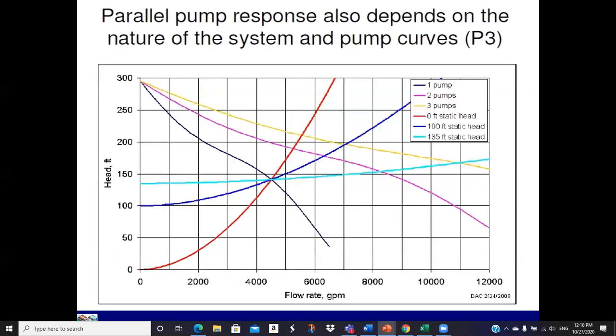So this just shows how parallel pumping works better with static dominated systems than it does with friction dominated systems. And then the point of this slide is to just do it for a different pump curve. And we see that with this pump curve, things work better, certainly for the static dominated system, and also for the all frictional system. So on the all frictional system, we're here. Second pump, we go on here. I don't know, what is that? Maybe 1,000 something GPM, not a whole lot. And then the third pump, we would go up here, which is only 300-400 more than we are here. So this system, while better than the previous pump curve, still is not very good in terms of all frictional system curves.